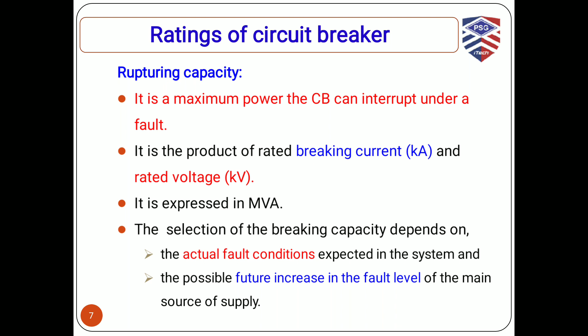It is, since being the product, expressed in MVA. The selection of the breaking capacity is based on the actual fault condition expected in the system in future, as well as the possible future increase in the fault level. So based on these two parameters, we'll select the breaking capacity of a circuit breaker. That is the main parameter to be decided as a rating of the circuit breaker.